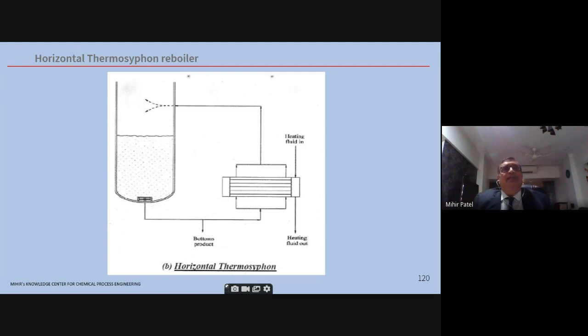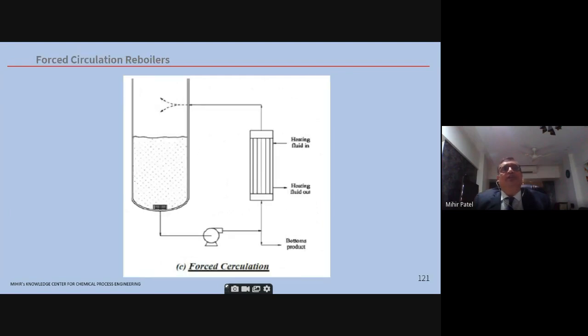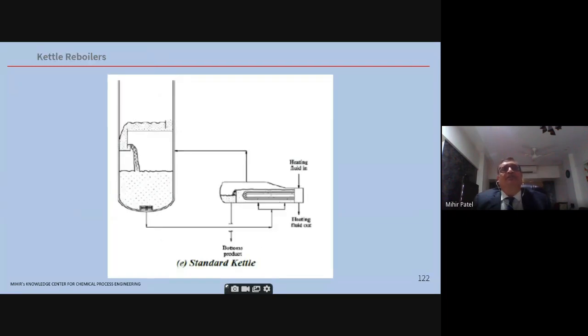This is a horizontal thermosiphon type. This is a forced circulation reboiler. It's nothing but a shell and tube. Now, at the outlet, you will have two-phase flow again, but the pump ensures that you have very good circulation. Then kettle reboilers. So here you see a kettle reboiler, full vaporization is occurring, and the lean fluid is going from the bottom. So this is used in, for example, amine regeneration unit, where you have the amine from the regenerator bottom comes to the kettle reboiler. The water is boiled up, and the lean amine goes out from the bottom for the amine absorber again.